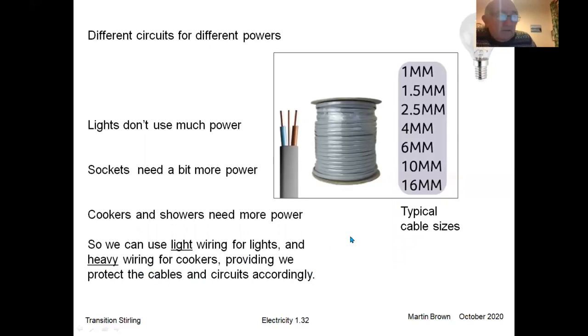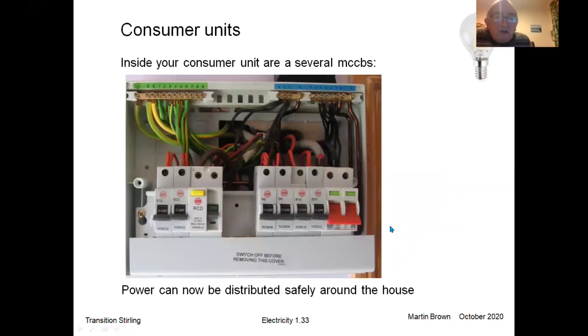things accordingly. So when we look in our consumer unit, what we see is a row of these circuit breakers. We see a main switch as well, and we see an RCD, and I'll talk about the RCD in a minute. The main switch obviously switches the whole house off. So if you operate that switch, all these switches are normally up, by the way, when everything's working. If you open that switch, that's simple. That's a straightforward mechanical switch.